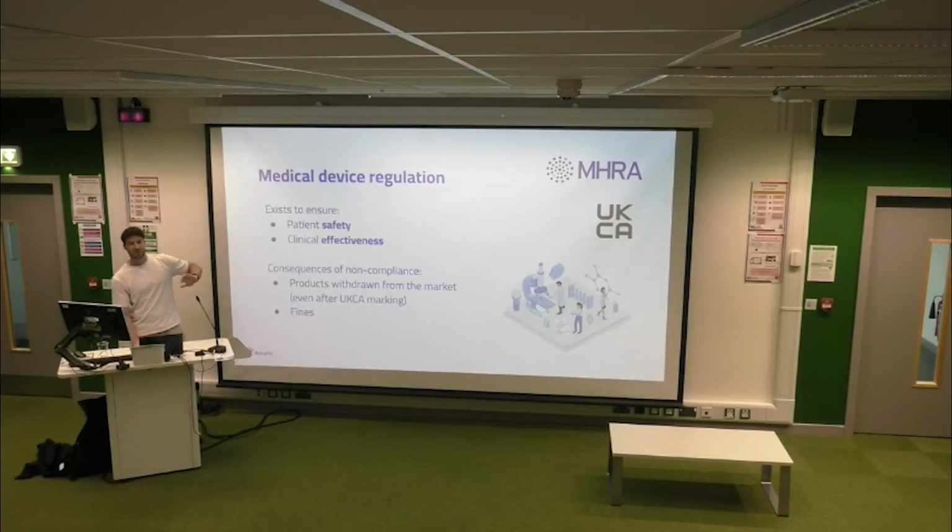Like everything we've spoken about, there are consequences of non-compliance. This can be products being withdrawn from the market. This can happen after achieving certification. So there's a requirement around post-deployment monitoring and post-market surveillance. And then if it's not met, these products can be withdrawn, and that's not uncommon. And similarly, like the ICO, you can get fines from the MHRA.